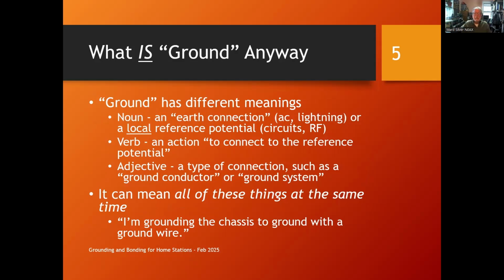It can have many different meanings. It can be a noun, which is referring to a connection to the earth, an earth connection. And when you're talking about AC or lightning protection, that's generally what you mean. It can also just be a local reference potential or voltage. For circuits, they talk about analog ground or digital ground or circuit ground. What they're just talking about is the local reference voltage, whether it's 0 volts with respect to the earth or 100 volts with respect to the earth. You don't know. It's just the reference voltage.